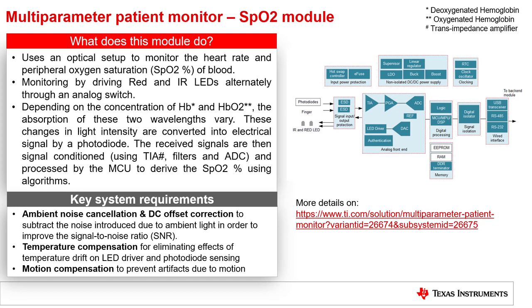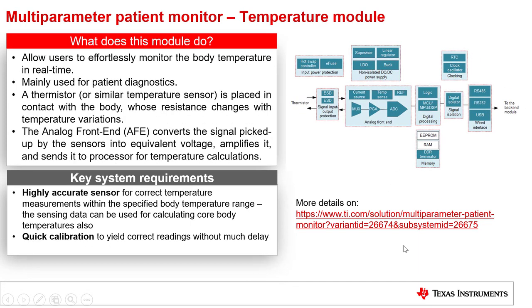A common block diagram for such SpO2 modules is shown in this slide. The third module is the temperature module. This module allows users to effortlessly monitor the body temperature in real time. It is mainly used for patient diagnostics. A thermistor, or similar temperature sensor, is placed in contact with the body, whose resistance changes with temperature variations. The analog front end, or AFE, converts the signal picked up by the sensors into equivalent voltage, amplifies the signal, and sends it to the processor for temperature calculations.